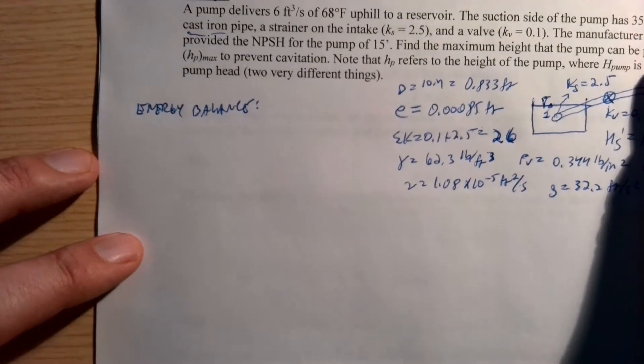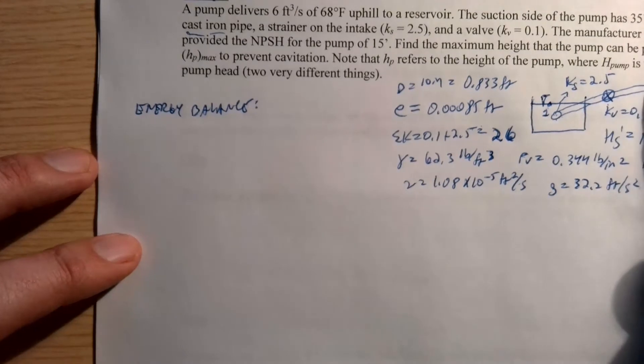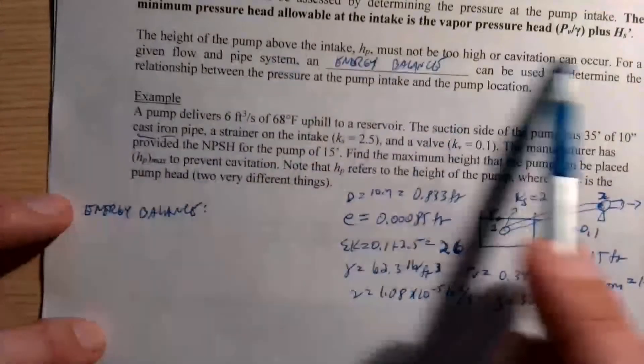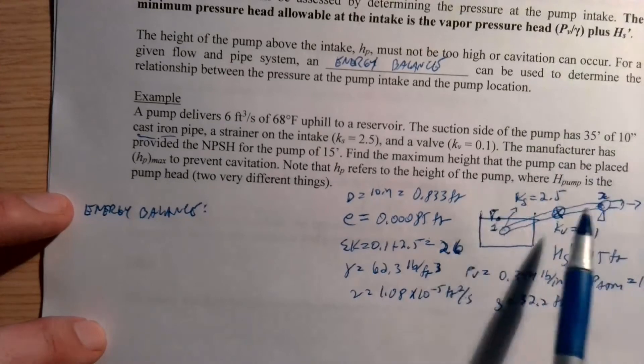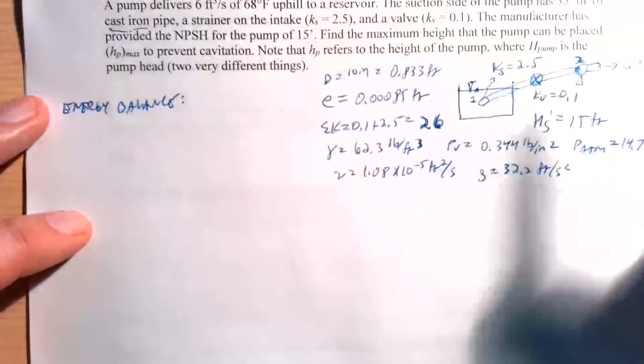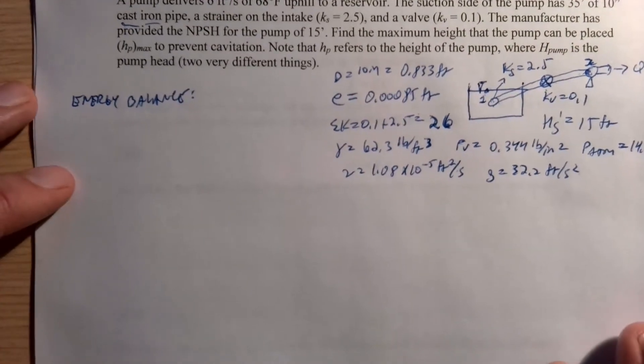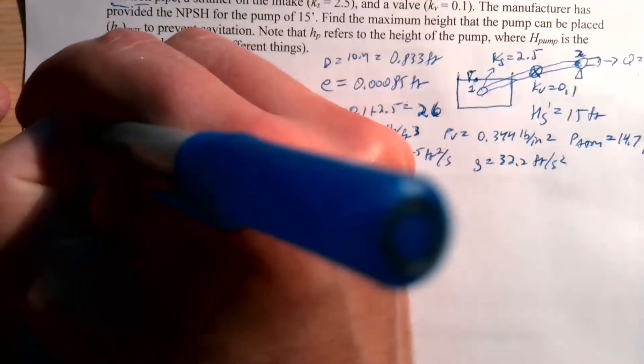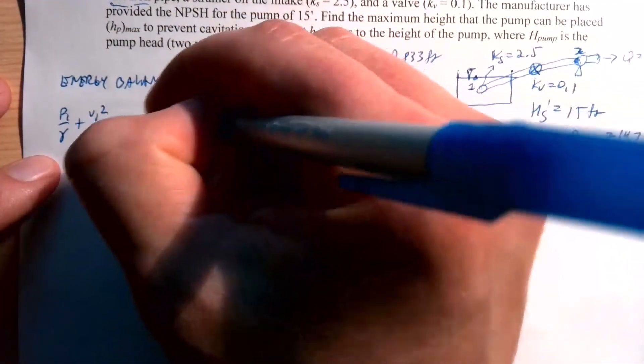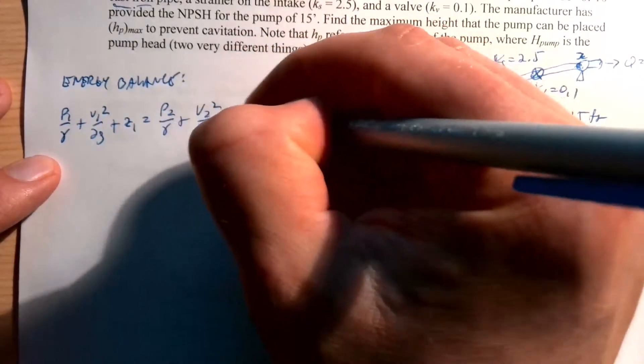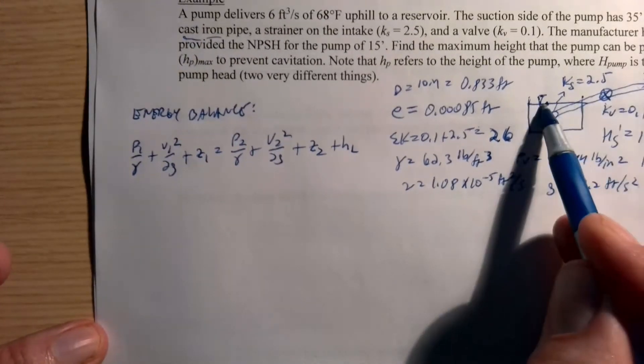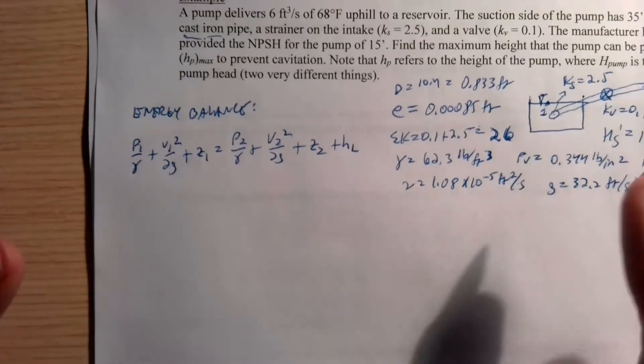What we need to know is the pressure right before the pump. The key condition is that at point 2, the pressure must equal P_v/γ + HS prime — that's the minimum allowable pressure. We need to make sure that condition is met, so we set up the energy balance to find the pressure there given the known flow rate.